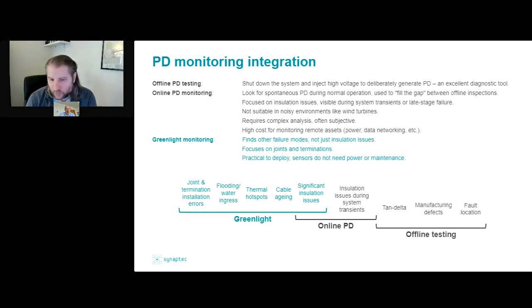There is one operator at least looking at the PD data only when there happens to be a transient on the cable - so it could be during a lightning strike or a switching transient, and that induces a high enough voltage where there's meaningful PD generated if there's some kind of defect in the system. So it can also see if there's a very serious issue that's really close to failure. That's where an online PD can give you some useful information. But again, that might be too late because the system's already in jeopardy at that point.